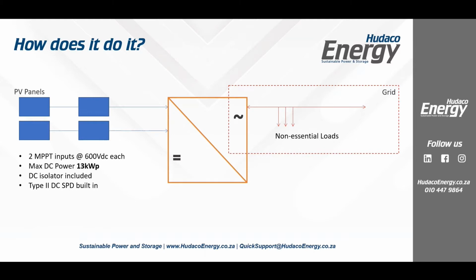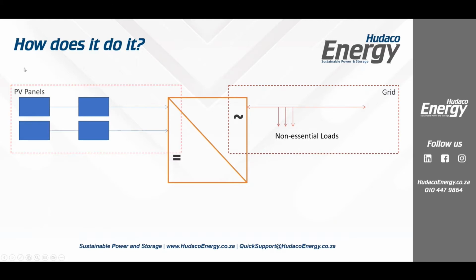My only recommendation would be during the installation, from a safety perspective, if you've got the panel sitting somewhere else, you may want to say, well, I actually want to put in an external box here where I can isolate the modules because they're not right next to the inverter. Of course, if they're right next to the inverter, it might be a different story. Again, that's a decision the competent person would make to say, well, technically we have protection, technically we have isolation. Do we want some next to the panels if it's not within arm's reach or not within view of the inverter itself? Okay, so that's our PV panel input. Then we've got our batteries, and our battery storage sits over here.